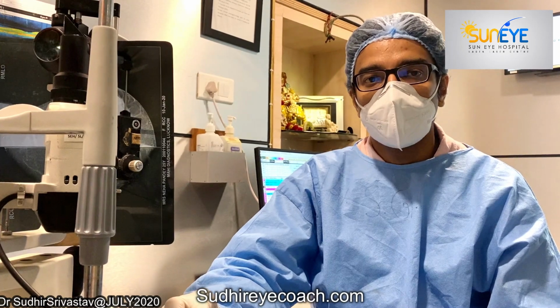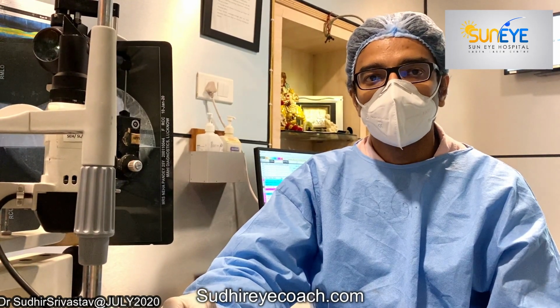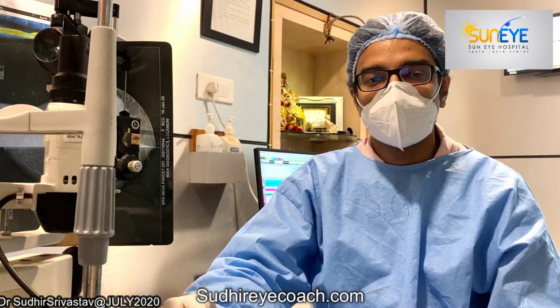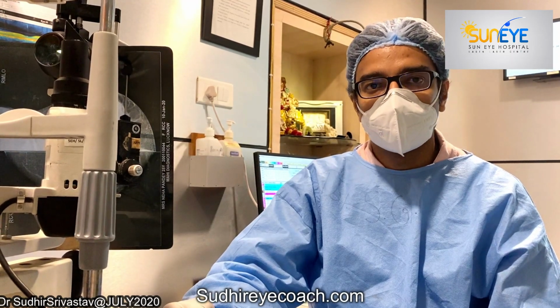Today I will discuss how to calibrate the applanation tonometer. As we all know, applanation tonometry is the gold standard for measuring the intraocular pressure. But with time, the calibration of the applanation tonometer is lost and it starts giving inaccurate readings, which are usually falsely higher IOP measurements. Therefore, it has to be calibrated from time to time, and usually it is done once in a month.